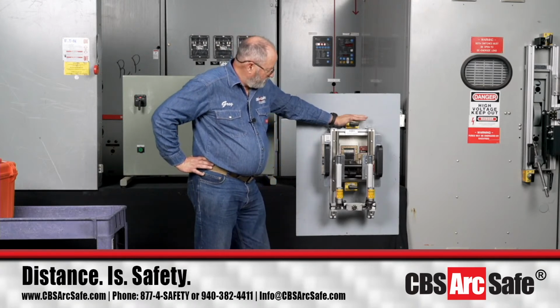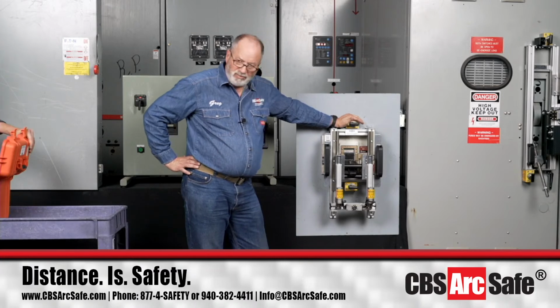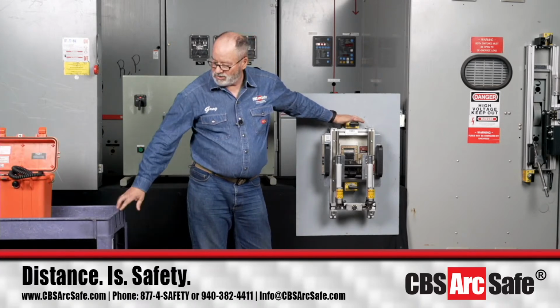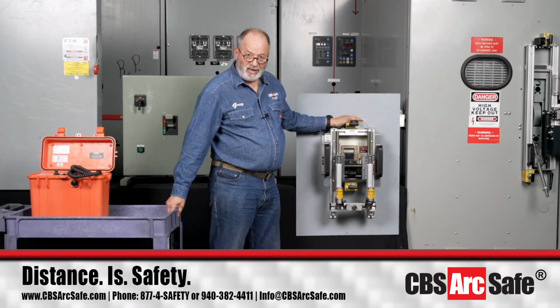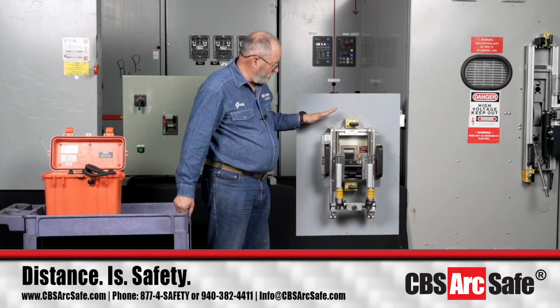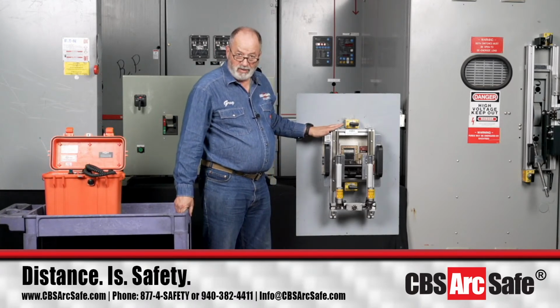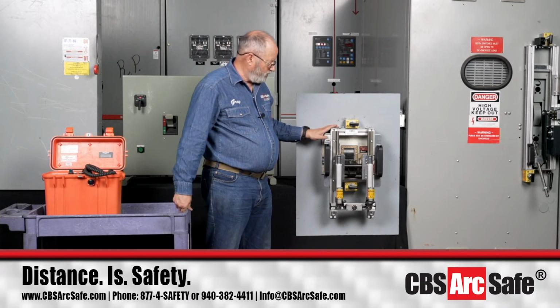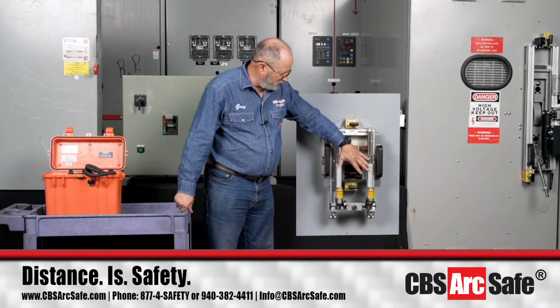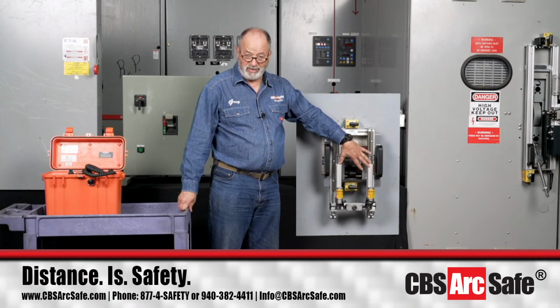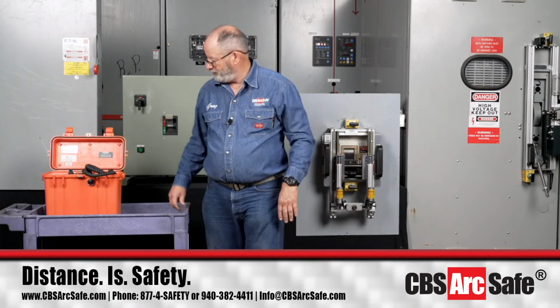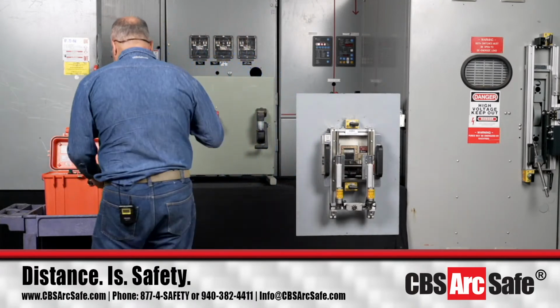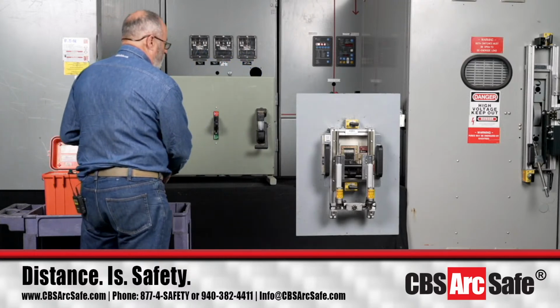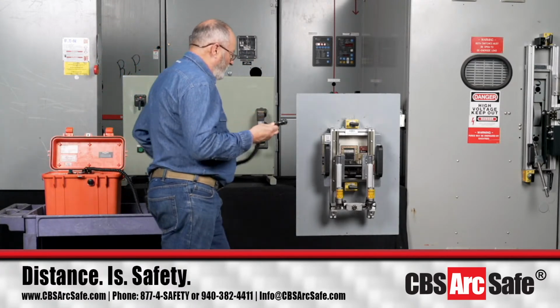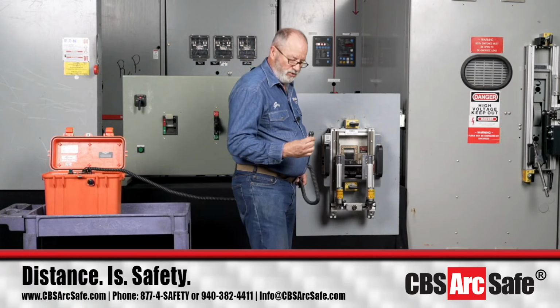This frame size, I think it runs 2,000 up to 3,000 amps, so you may have varying amp sizes, but the breaker itself remains the same. It's one of the stronger breakers, which is why you're going to see 2 actuators here to push this up and down. We usually see these used as a main on some motor control centers, so that's where you're going to find it used a lot.